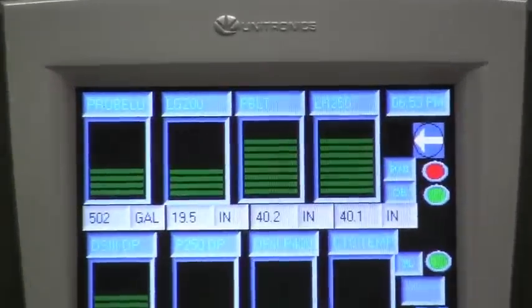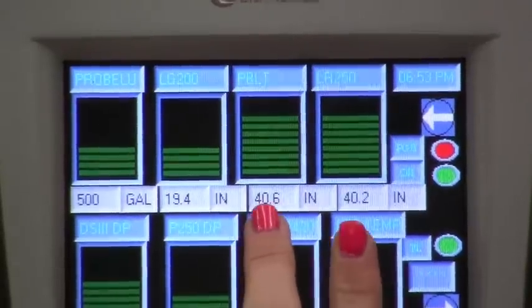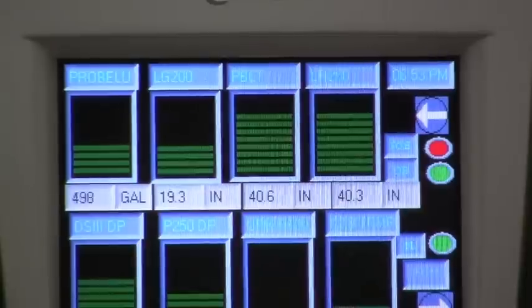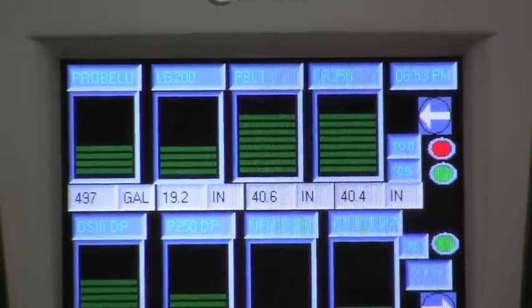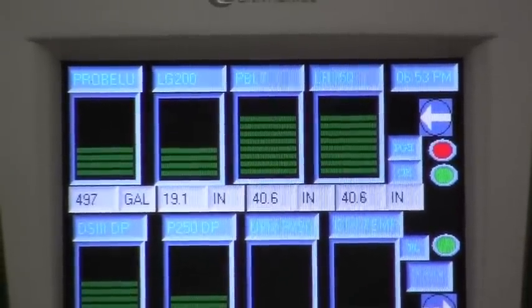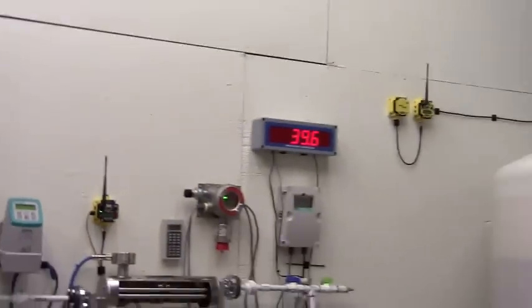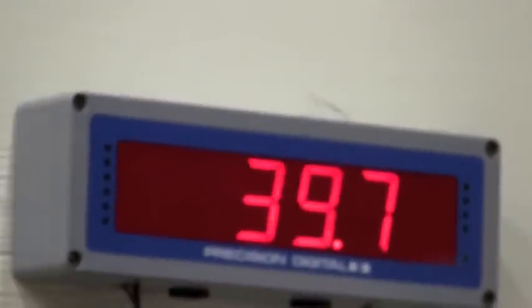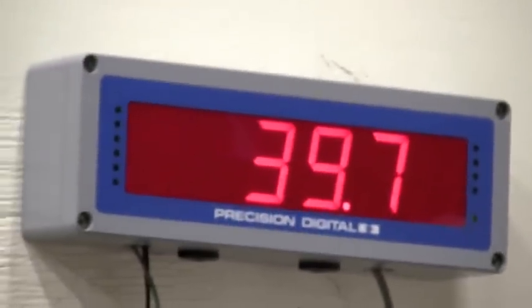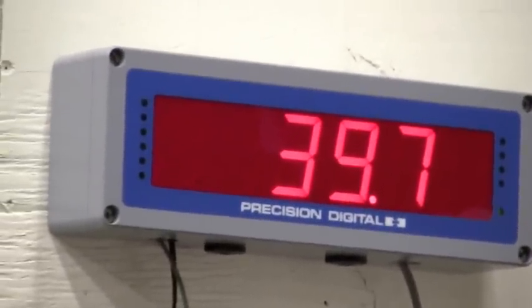Now we're looking at the top 2 right side measurements. Those are our two level transmitters that are in the same tank. You can see they're reading within a couple tenths of an inch of each other. We also have a third level measurement in that tank. If we go over to the Siemens HydroRanger 200, you'll see it's reading about the same as well.